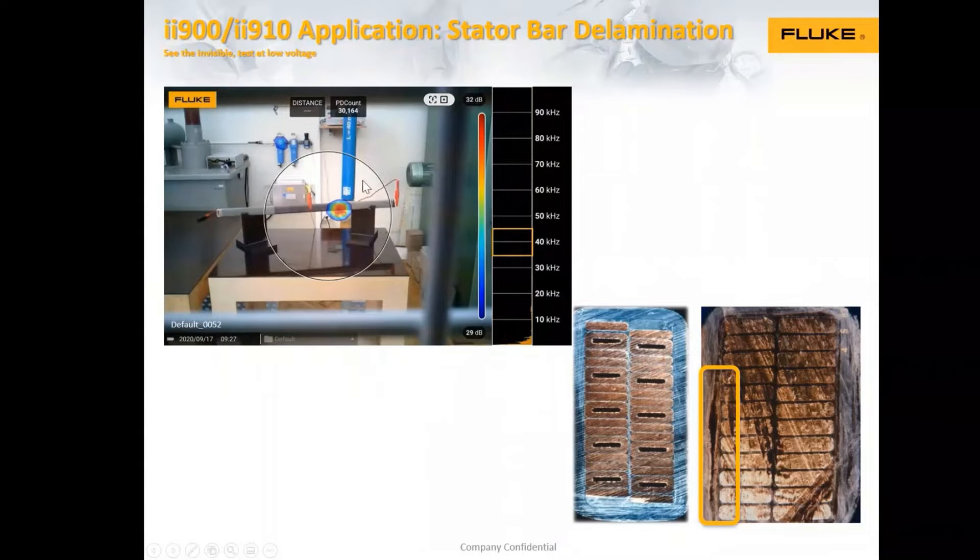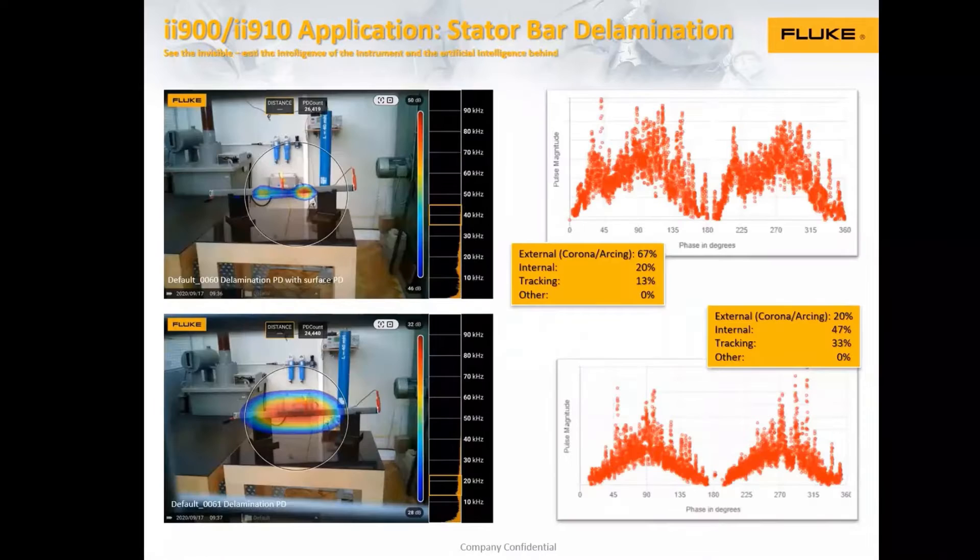I like this example here very much, because we see here the PD, and at the same time, we see here an armature that is leaking. This one here is measured with the acoustic camera at the same time. It's not only PD that we see, and we made a test at higher voltage, and we got this figure here, and we got this figure here at the same voltage.